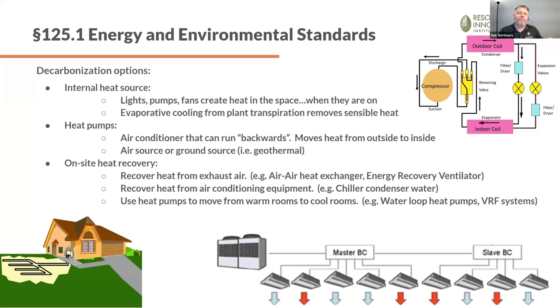That's the premise of the last one: use heat pumps to move heat from warm rooms to cool rooms. There are technologies like water loop heat pumps and VRF, variable refrigerant flow devices—basically multiple little heat pumps. Think of it like having a couple of flower rooms with lights on and a couple with lights off. I have excess heat where the lights are on, but I need heat where the lights are off. I simply use water or refrigerant to move that heat from one room to the other. Instead of pulling heat from outdoors or generating it with a furnace or boiler, I'm just removing heat I already have from where I don't need it to where I need it. There are lots of technologies out there—don't be afraid, you might have to work with an engineering firm or architect, but there are lots of options.